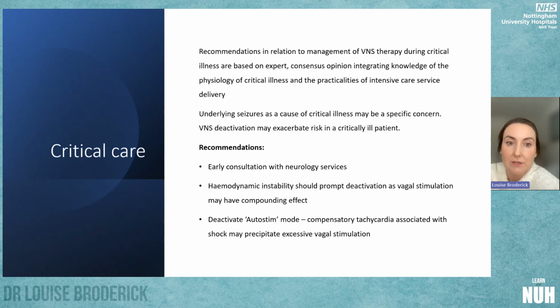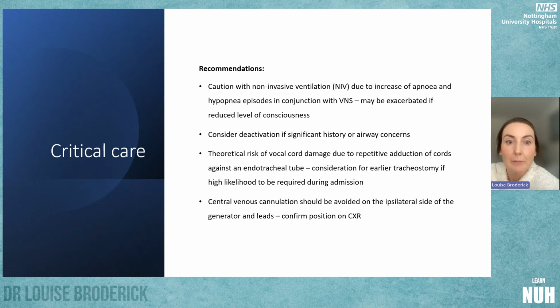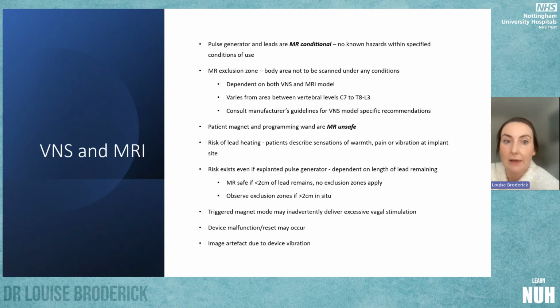So, early consultation with neurology services, and have a low threshold for deactivating the device with hemodynamic instability. Deactivate auto-stim mode, which could potentially cause excessive vagal stimulation in the setting of compensatory tachycardia associated with shock states. Be cautious with non-invasive ventilation due to the risk of apnea and hypopnea in conjunction with the VNS, which may be exacerbated if there is a reduced level of consciousness. Consider deactivation if any risk of airway concerns. We've also put in a vague recommendation with regard to tracheostomy. If a patient is likely to need a tracheostomy, it may be considered earlier due to the risk of vocal cord damage from repetitive adduction of the cords against the endotracheal tube. And of course, when you're putting in lines, avoid the ipsilateral side of the device.